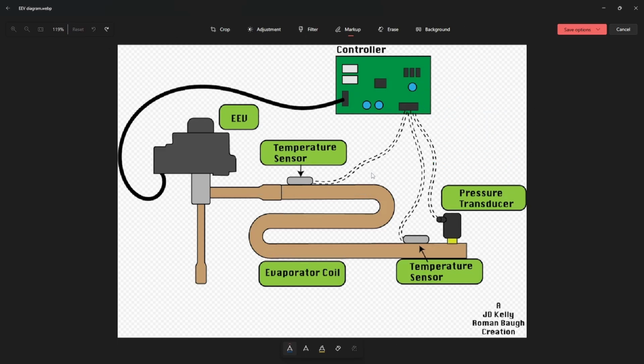So a lot of inverter-driven systems will have a dedicated mode called oil return mode. If you have an oil return mode, you need to know what suction pressure you're reading, so that way this board can calculate if the velocity of the refrigerant is going to be enough to move the refrigerant oil out of the coil back to our compressor. A lot of times when a system goes into oil return mode, it will shut the fans off and literally just run the compressor by itself just fast enough to be able to pull that oil from our coil back to the compressor sump so that way we can keep everything properly lubricated.